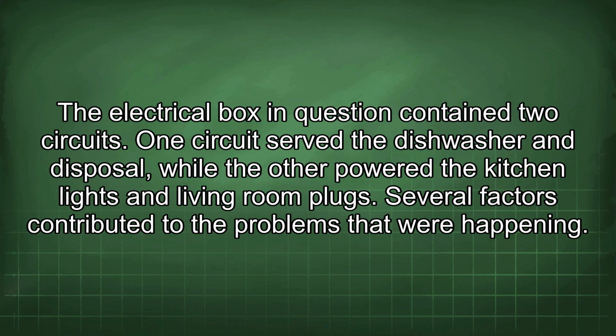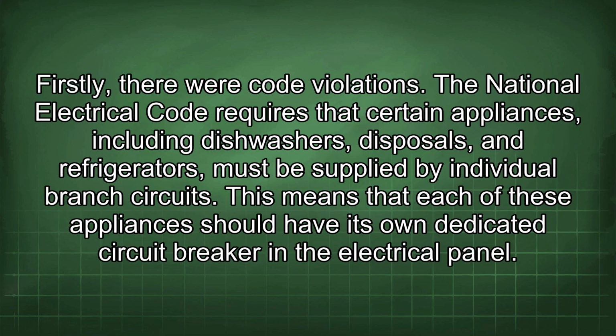Several factors contributed to the problems that were happening. Firstly, there were code violations. The National Electrical Code requires that certain appliances, including dishwashers, disposals, and refrigerators, must be supplied by individual branch circuits. This means that each of these appliances should have its own dedicated circuit breaker in the electrical panel.